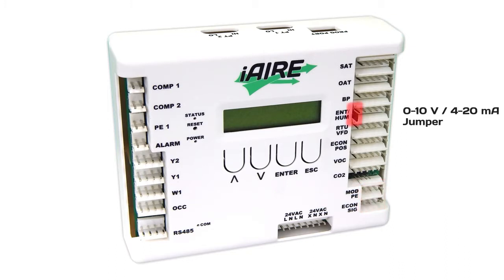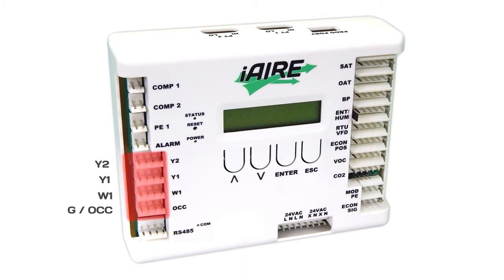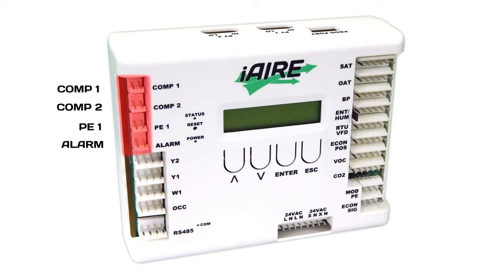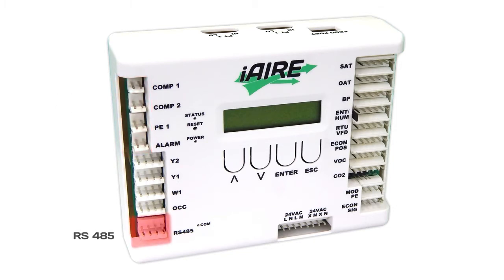You can change from 0 to 10 to 4 to 20 milliamp by putting a jumper on the tab beside the controller on the right side for these analog inputs and outputs. There are 4 digital inputs located on the left-hand side of the controller. There are 4 digital outputs located on the left side of the controller. There is an RS-485 port used for communication between the controller and other devices when required. A programming port is located on top of the unit.